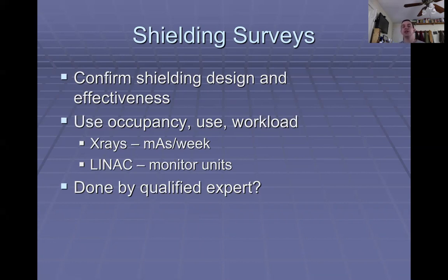A lot of machines will have times where they put out very intense radiation, and you can get large numbers. You can go well past 10 millirem per hour. But remember, it's 10 millirem in a week. So if you have a dose rate of 100 millirem per hour, you might think, oh, that will give them 10 millirem in a week very quickly. But if that machine is on for seconds at a time or minutes a day, then it's very possible that you'll never actually reach that hour of irradiation.